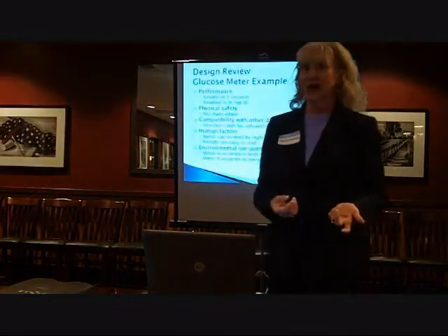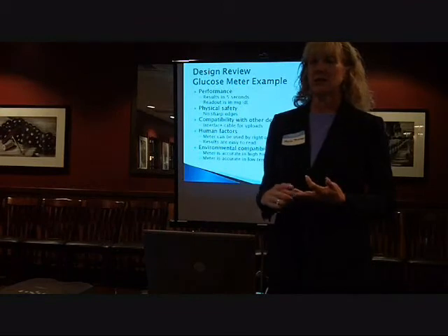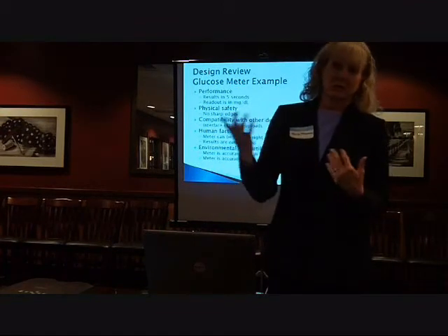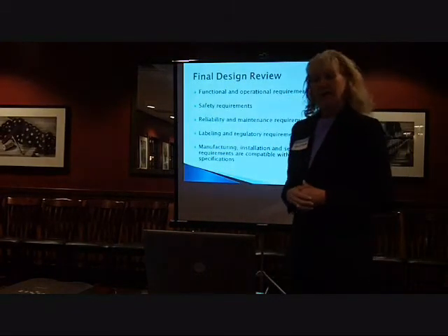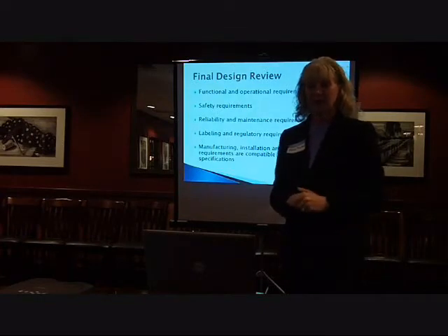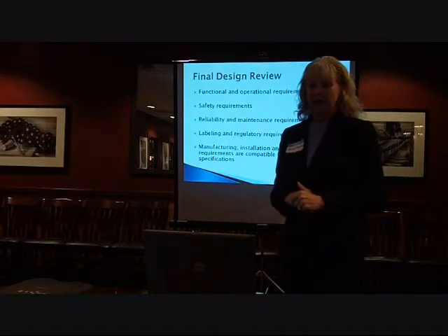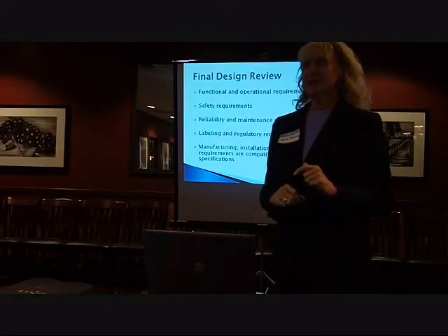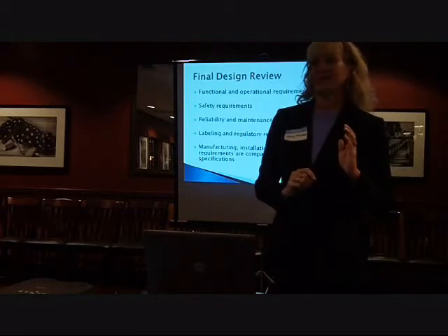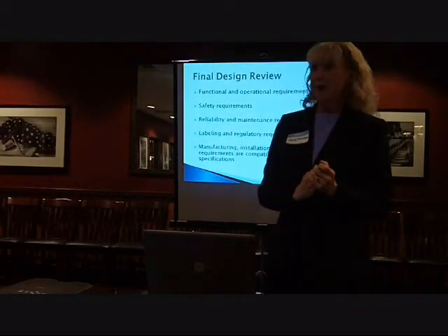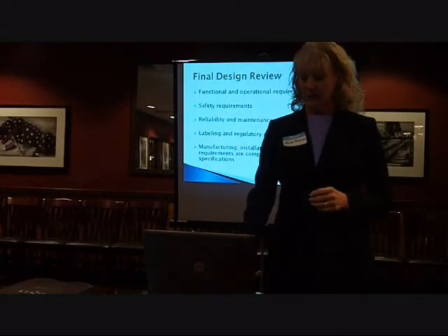Environmental issues are also very important. These would be things that would be in the design requirements. It's going to be exposed to these temperature ranges, these humidity ranges, altitude ranges if it's going to be shipped that way. And again, in the final design review, you are being very comprehensive. Reliability and maintenance come in here, and the manufacturing, installation, servicing. You're really looking at this device from when you begin to make it until it gets to the customer, and perhaps back to you if it's something that needs repair.